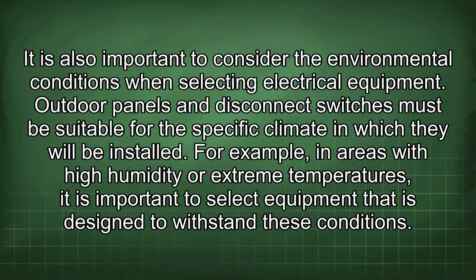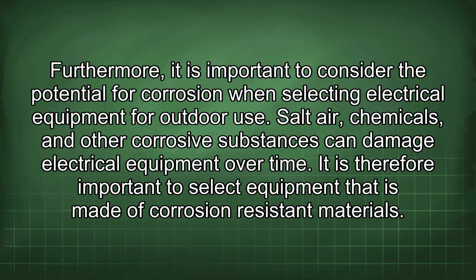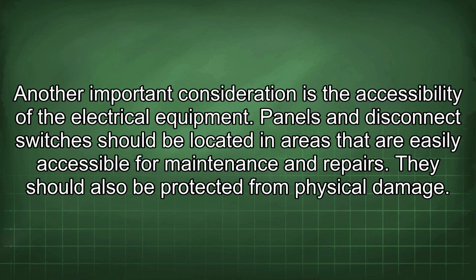withstand these conditions. Furthermore, it is important to consider the potential for corrosion when selecting electrical equipment for outdoor use. Salt air, chemicals, and other corrosive substances can damage electrical equipment over time. It is therefore important to select equipment that is made of corrosion-resistant materials. Another important consideration is the accessibility of the electrical equipment. Panels and disconnect switches should be located in areas that are easily accessible for maintenance and repairs. They should also be protected from physical damage.